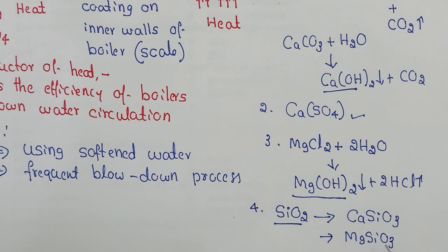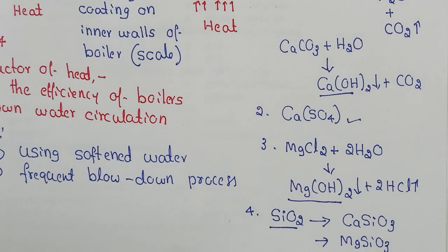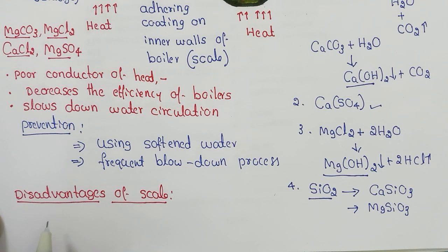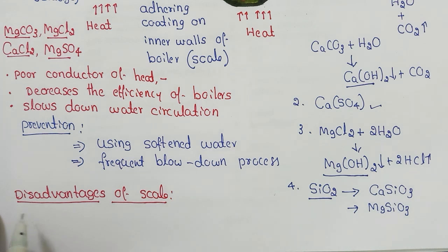One important source of silica in water is the sand filter — used to filter larger impurities, but small amounts of sand enter the boiler feed water and combine with calcium and magnesium salts to form highly adherent calcium silicate and magnesium silicate scales. Similar to sludge, scales also cause several disadvantages, including wastage of fuel, because scales are bad conductors of heat.